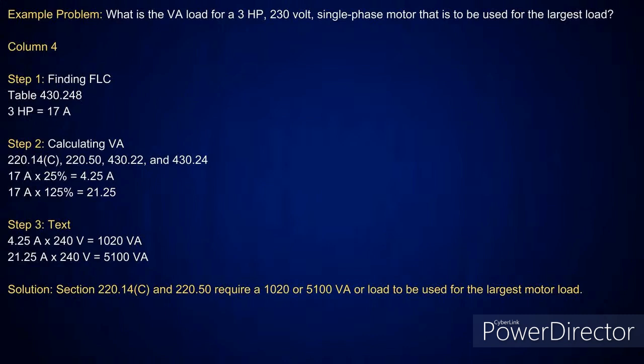Now, if I just took the whole 17 amps at 125%, it would be 21.25 amps. The way to prove that is if I took 17 amps at 100%, that's 17 amps. You add the 4.25 on it, it's 21.25 amps. So there are two different ways. If you guys want to do it different ways, you could do it two different ways. Basically, once I've done all the calculations, I just do it at 125%, and I'm done with it. That's the way I do it. People say, well, how do you get the 25%? Just put 125% on the largest motor, and you're done. So I'd have 21.25 amps. It's a 120/240 volt system. That'll give you 5100 VA. Then just add all the other motors up at 100% and you're done.